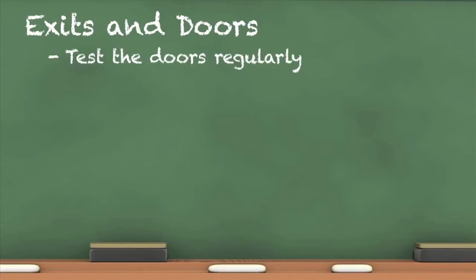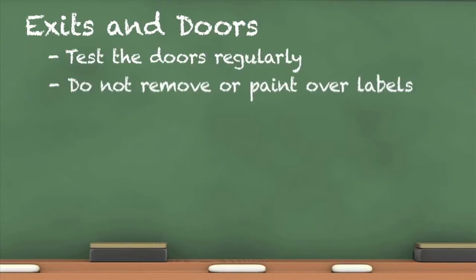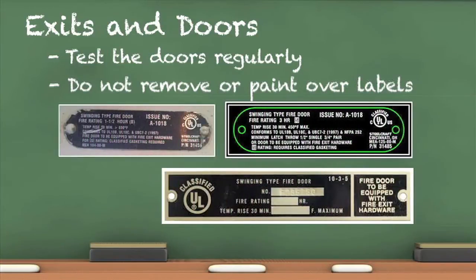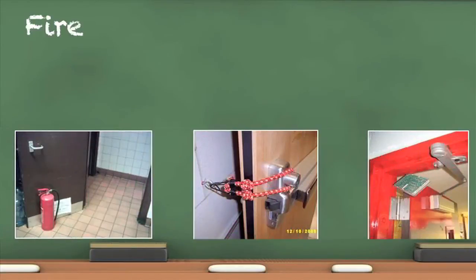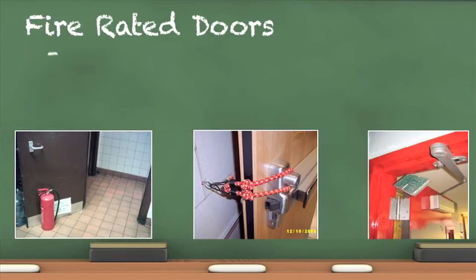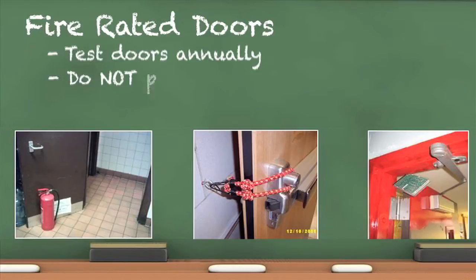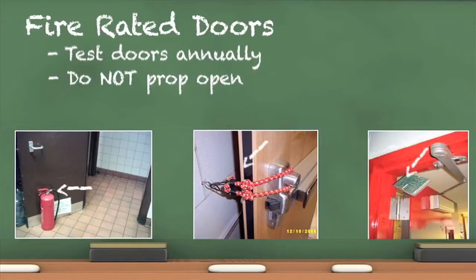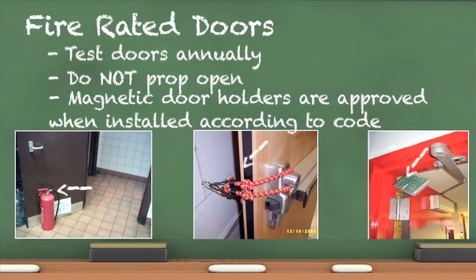Test the doors regularly to make certain they function properly. Do not remove or paint over any fire door labels on the door or door jamb. Fire doors are a very important fire-rated assembly — they help keep smoke and fire compartmentalized, but only when they function properly. Doors should be inspected annually at a minimum and repaired or replaced whenever damaged. Fire doors should self-close and latch and may not be propped open. When installed with permits and according to code, magnetic door holders may be used to hold fire doors open. When devices detect fire or smoke, the magnet releases the door and it should close and latch automatically. Magnetic hold-open devices require periodic testing and maintenance.